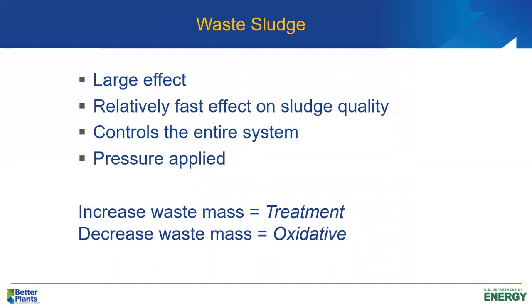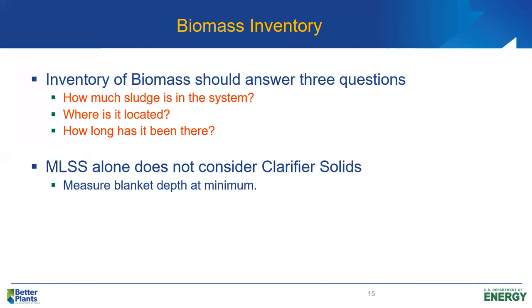We use waste sludge as our primary control mechanism and use it to apply pressure to the process. We can apply a treatment pressure by increasing the amount of waste mass — this makes more food available to each microorganism so they grow faster, and the sludge tends to be under-oxidized. On the other hand, if we decrease the waste mass, that is an oxidative pressure — we tend to have a lower F/M ratio, less food for each bacterium, and the sludge tends to be over-oxidized. We may need to apply either type of pressure depending on how our process is operating.